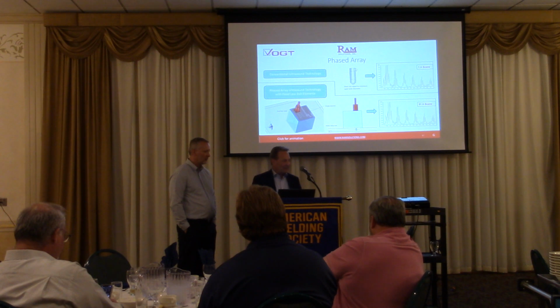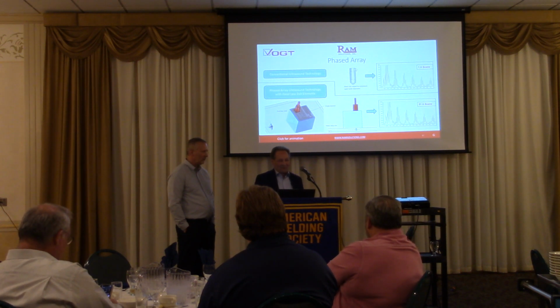So the operator runs around with a pocket full of probes if he has to test a lot of different thicknesses and different minimum diameters. By this minimum diameter, we achieve, if the spot is big enough, that we only get the signals from the back wall. So clear back wall echo reflection without any reflections from the interface.